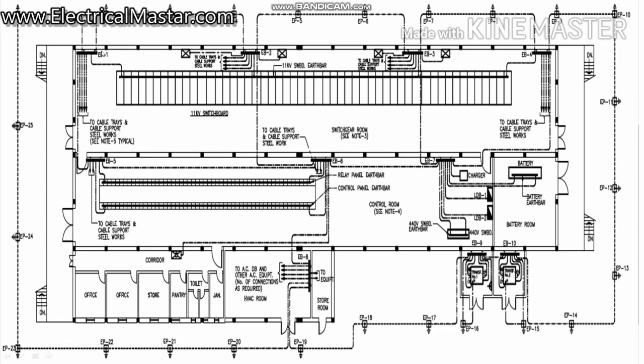And see here, inside the substation they mounted earth bus bars, numbered EB1, earth bus bar 1, earth bus bar 2, earth bus bar 3, 4, 5, 6, 7, 8, 9 and 10. So a total of 10 earth bus bars are used. As per the standard, each earth bus bar must have 2 incomers from the earth pit connection. See here EB1, it is taking from earth pit 1 and earth pit 2. Both incomers are connected to EB1, and the distribution goes out in numbers from there.